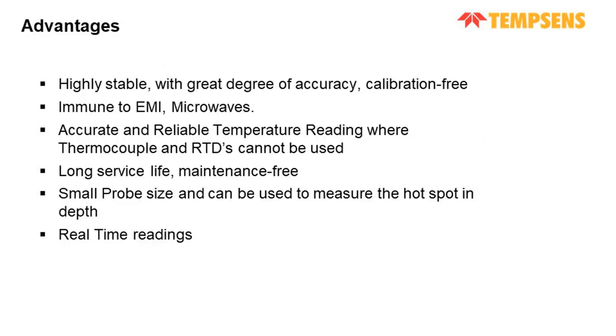So the major advantages of a fluorescence-based system are that it is highly stable with a great degree of accuracy, and it is calibration free. It only needs to be calibrated once, and then it can be used for the application. It is immune to EMI and microwaves. The readings are accurate and reliable where thermocouples and RTDs cannot be used. So where thermocouples and RTDs fail, we can use fluorescence-based systems. It has a long service life of up to 10 years, and it is maintenance free. The fiber sensor size is very small and can be used to measure the hotspot in depth, and it provides real-time readings.